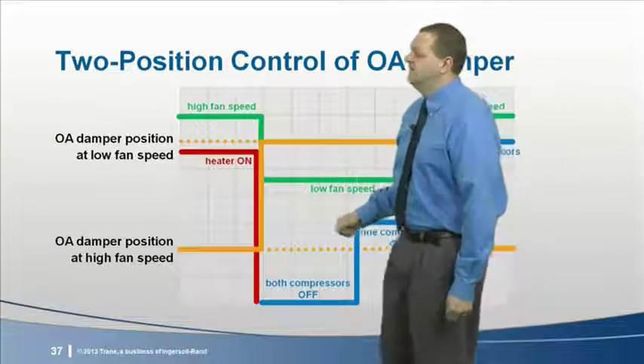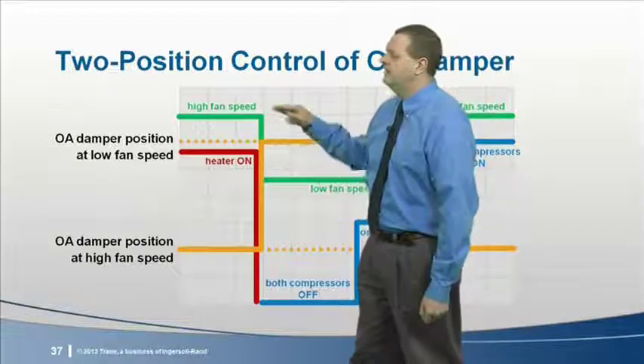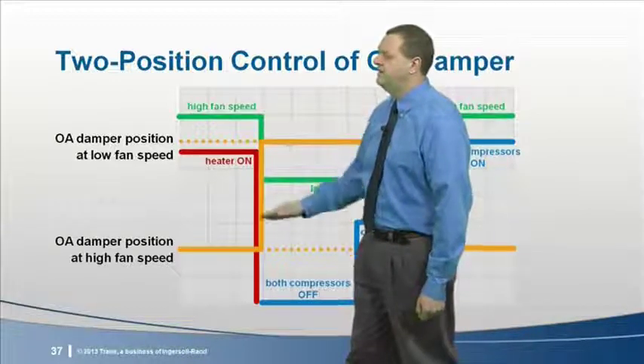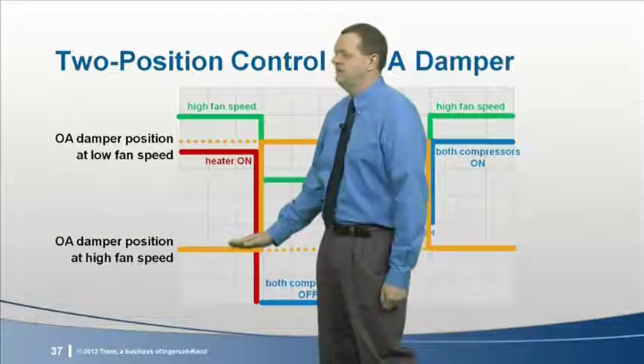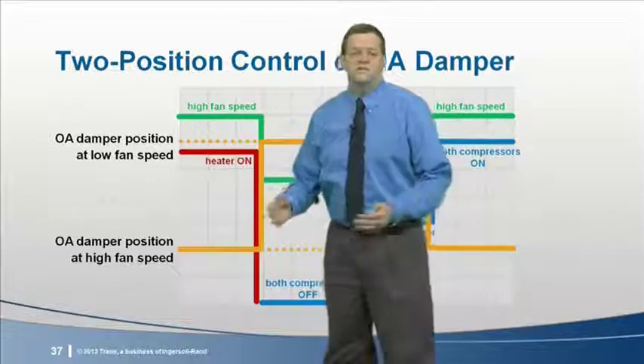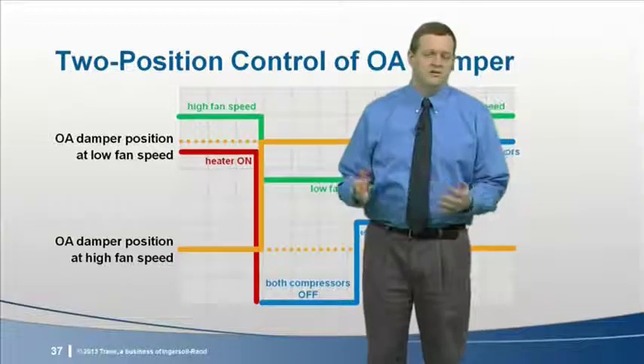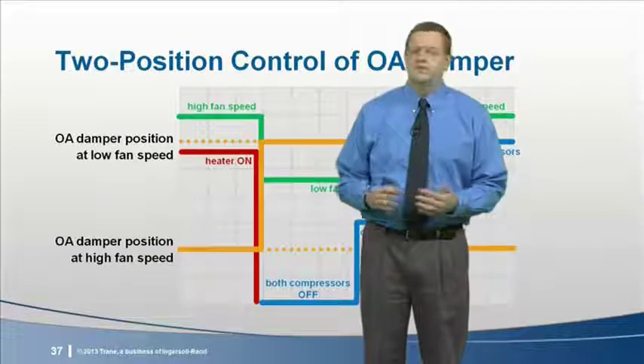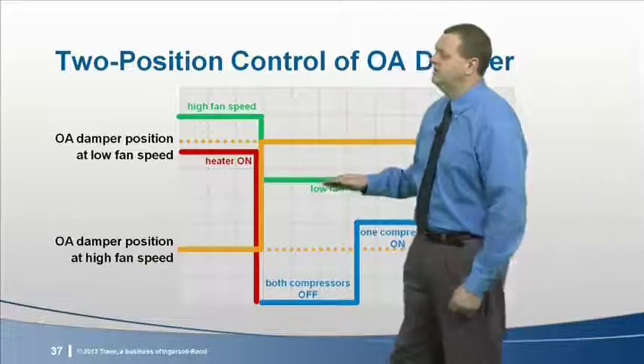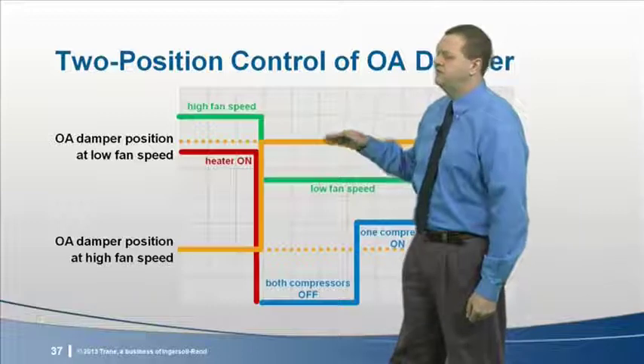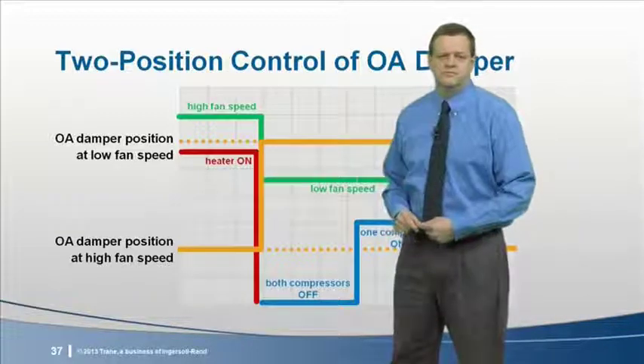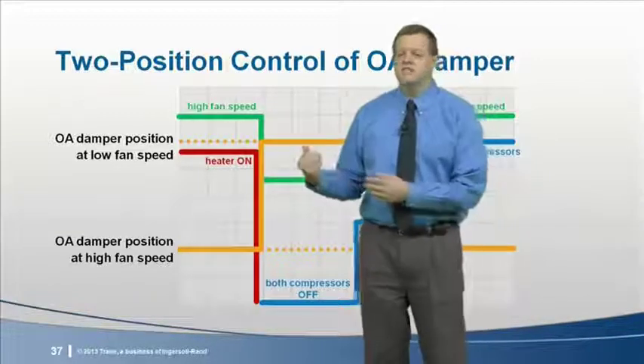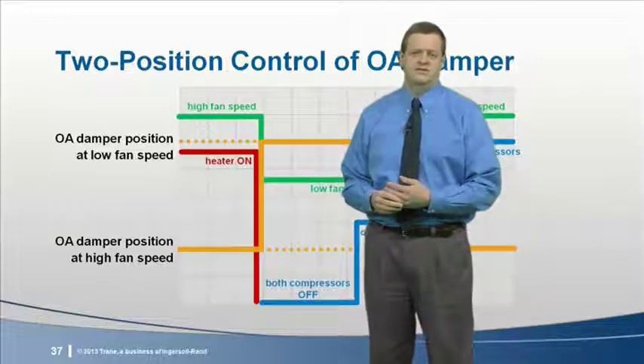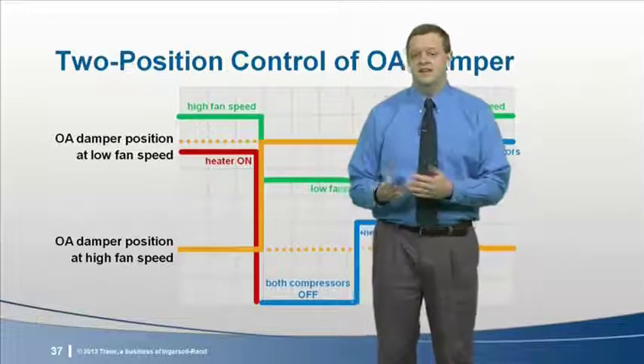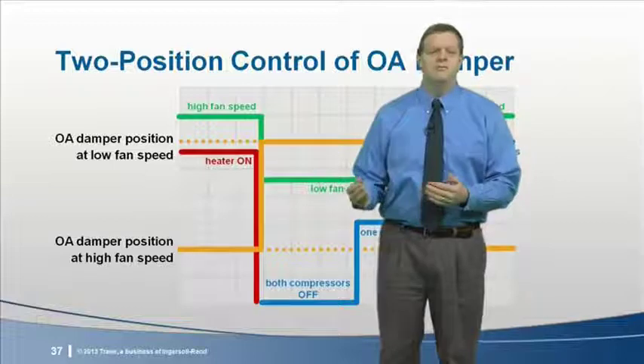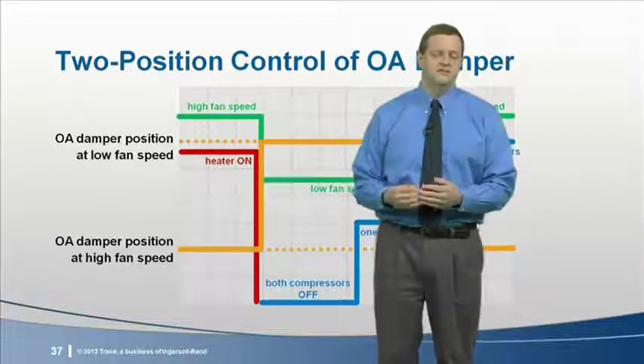When the heater is activated and the fan is again operating at high speed, the damper position changes back to the original setting. So fan speed and damper position are controlled together. Whenever the fan runs at low speed, the damper is open to this further open position set point. Of course, these are minimum position set points. If the system uses an airside economizer, the damper may be opened further when conditions are suitable for economizing.